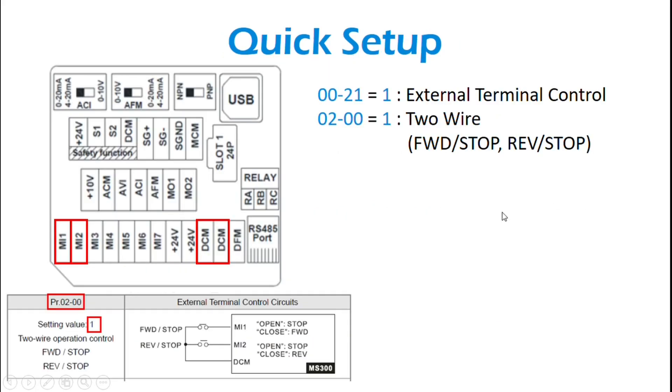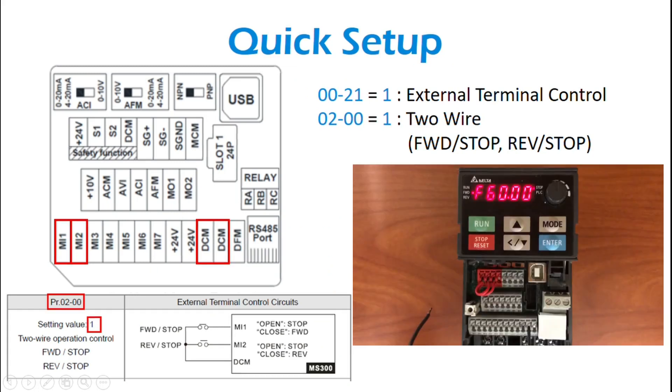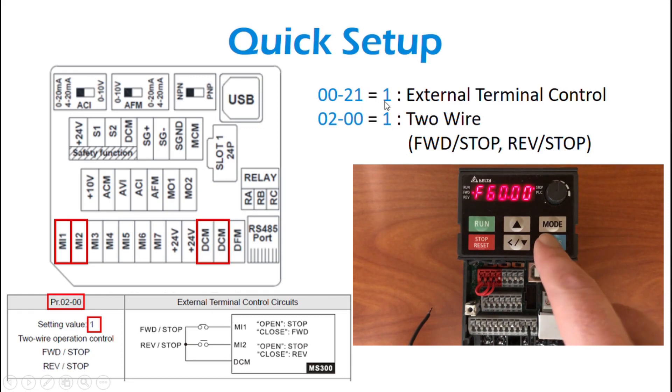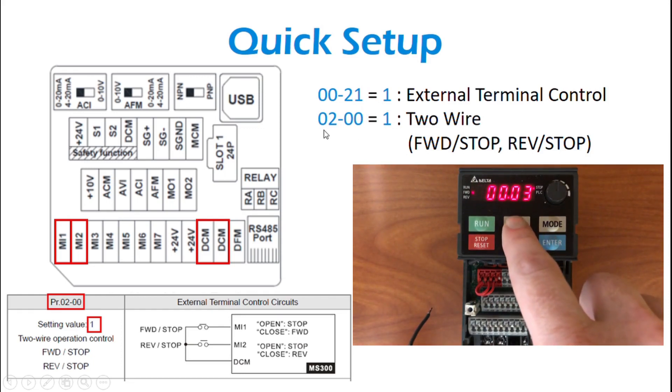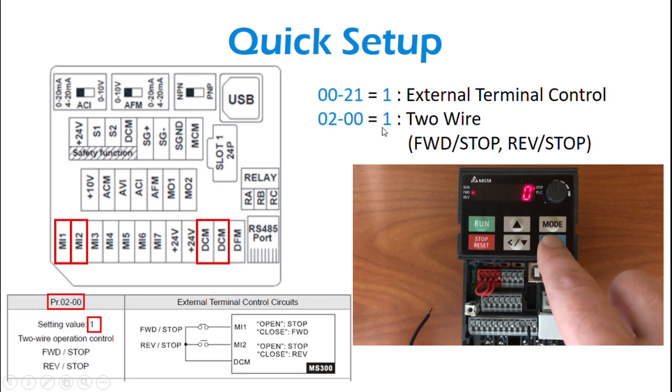So a quick setup on two-wire control. You've got these two parameters: 0021, you're going to set that to 1, and 0200, you're going to set that one to 1 also for a two-wire.